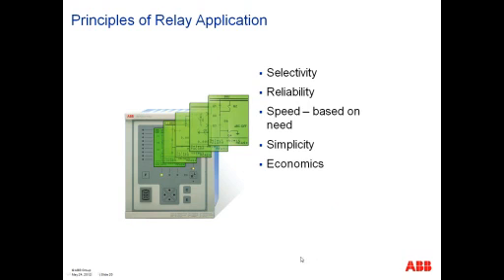The first and foremost is the selectivity. As I mentioned before in the history, initial protection was not very selective. You either tripped or didn't trip because the system you had burned down or you had a fuse blow or something like that. But the selectivity deals with minimizing the impact on the power system whenever you have one of these intolerable conditions. And the relay trips, you only want to trip and control just the minimum amount of area of the system to have that impact.